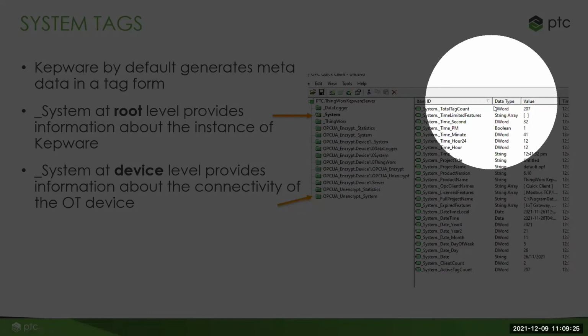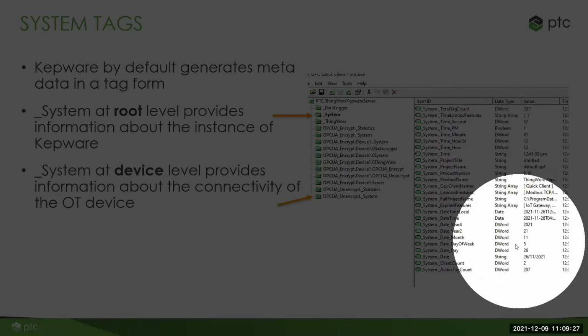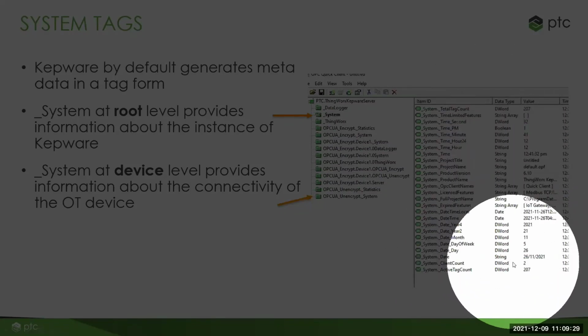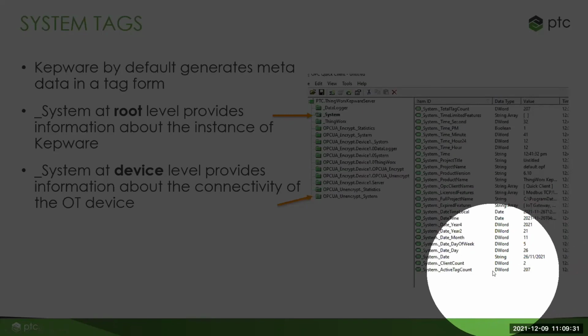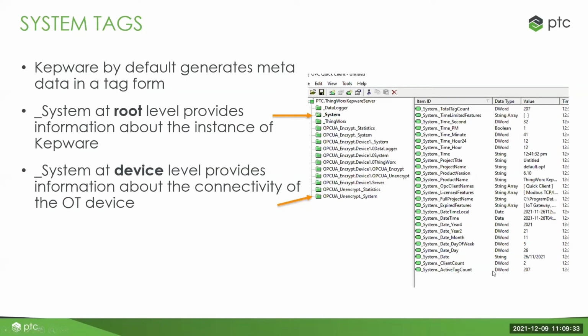underneath which you can see the data about the running instance of KEPServerEX. So you can see how many clients are connected. For example, you know that in this system there's only one HMI, maybe a redundant system, so there should be only 2 counts of Kepware in a normal operational status. So you can monitor this type for abnormal changes, right?